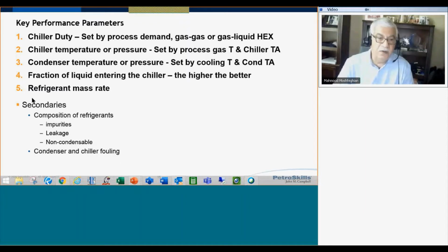There are other secondary parameters that influence power requirement of compressor, and that's composition of refrigerant, any impurities, especially light component impact or heavy component impact the compressor power requirement. And some of the contaminant may get in the system through leakage, and the non-condensable increases the condenser pressure and increases the power requirement. So condenser and chiller fouling again causes the power requirement to go up.